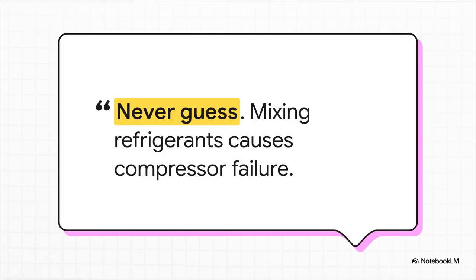Which brings us to the golden rule for the diagnostic phase. Whether you're doing a serial number lookup on the manufacturer's portal, checking the compressor tag, or using an electronic identifier tool, never, ever guess the refrigerant type. The consequences are just too severe. You're looking at compressor failure, oil sludging, and severe safety hazards, especially with the newer A2L gases.